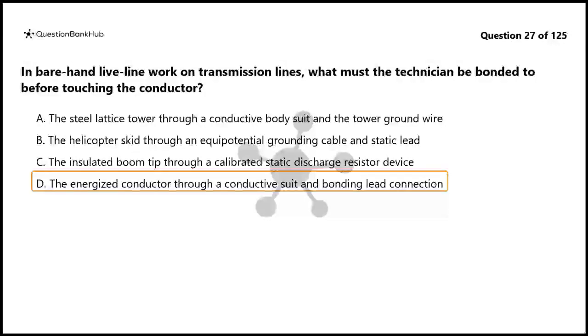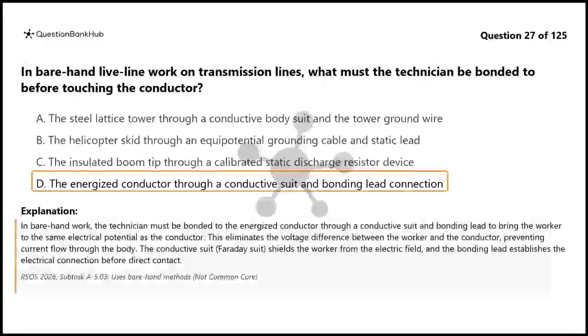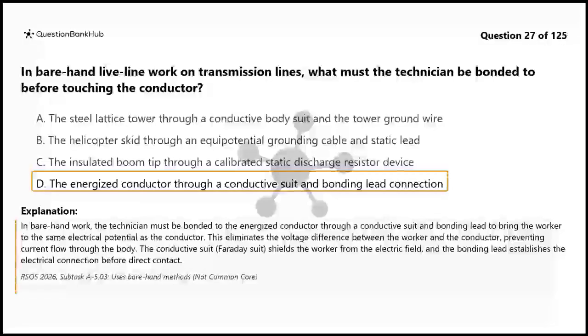The correct answer is D. In bare-hand work, the technician must be bonded to the energized conductor through a conductive suit and bonding lead to bring the worker to the same electrical potential as the conductor. This eliminates the voltage difference between the worker and the conductor, preventing current flow through the body. The conductive suit, Faraday suit, shields the worker from the electric field, and the bonding lead establishes the electrical connection before direct contact.